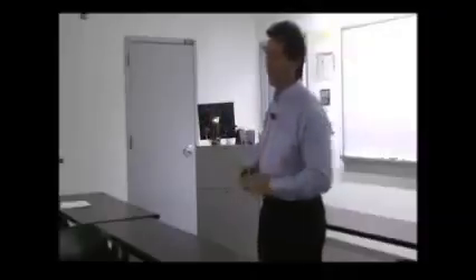If you ever looked at the evolution of ductwork construction, what did we have? I mean, go back in time. Paper, cloth. You ever see the tube ductwork? It's a big tube. They got all kinds of names, but they typically call it tube ductwork, right? I won't go there, right? Okay? He knows where I'm coming from. But again, what this is, it's collapsible ductwork. You turn on the air conditioning unit, okay? It pressurizes the ductwork. It goes back up into where it should be, right back into position, and it distributes air. You turn it off, it cycles back down, and it deflates like a big balloon, right?